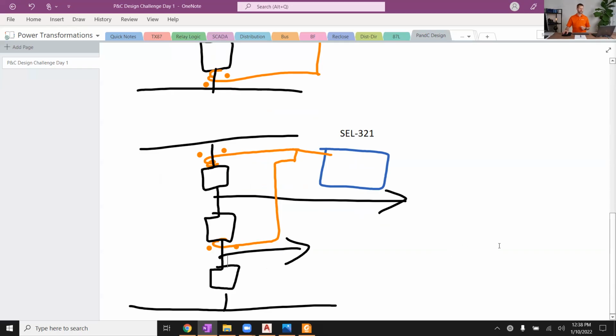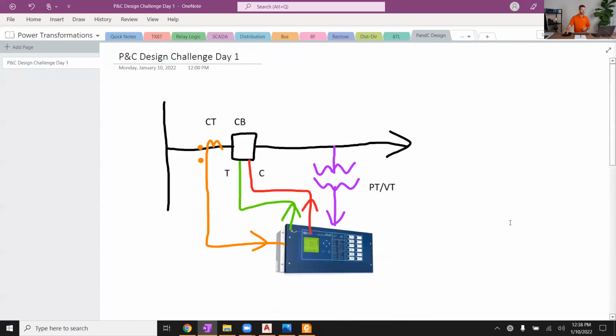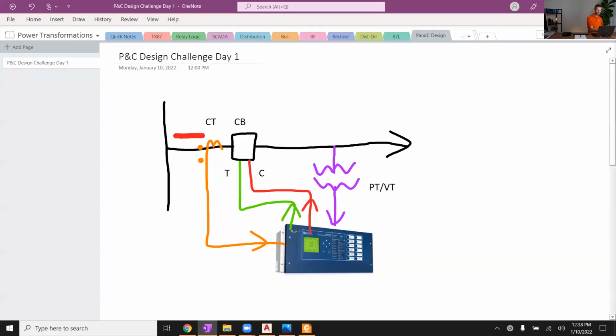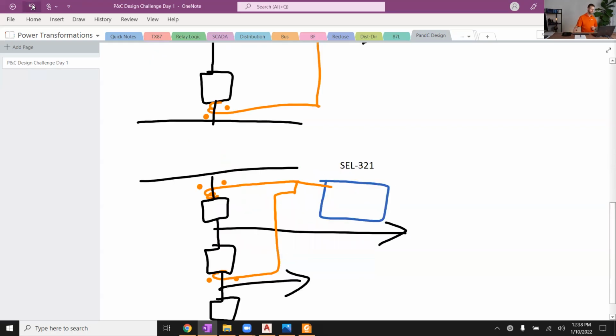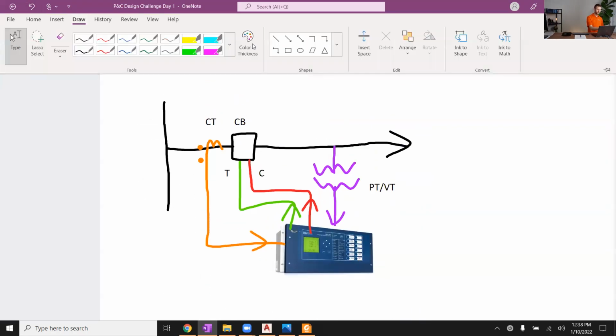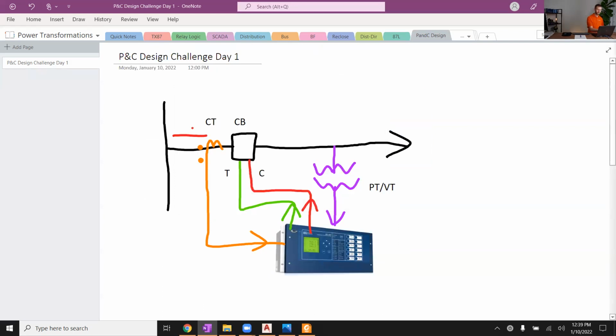The convention of the industry is that current into the primary polarity dot equals current out of the secondary polarity dot. I'm going to go back up to my simplified drawing up here for this. If I have fault current flowing in to my transmission line, let's go with that. Fault current flowing into my primary polarity dot, that's going to equal current flowing out of my secondary polarity dot. And the same is true, the inverse, the reciprocal of that. If you have current flowing out of your primary polarity dot, it's going to equal current flowing in to your secondary polarity dot.